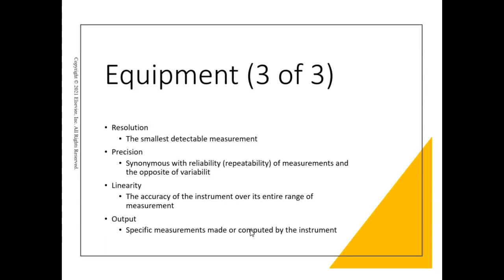Linearity is the accuracy of the equipment over the entire range of measurements. So not only the top range of that 3 liters, but testing it at like zero flow as well, just like you would do when you're testing your FiO2 analyzers, you're going to be looking at 21% and you're going to look at 100%. So that's kind of that linearity, I'm looking to make sure it's accurate at the bottom number of the range and the top number of the range.